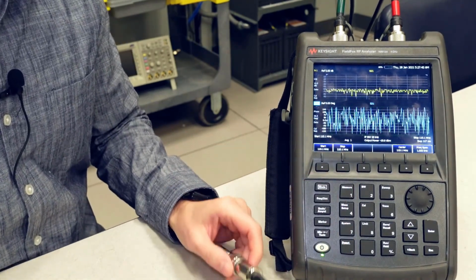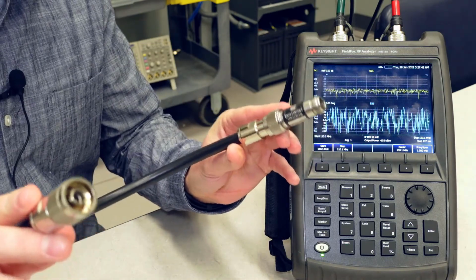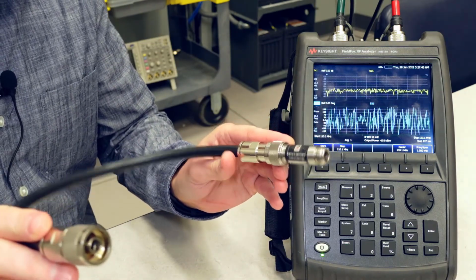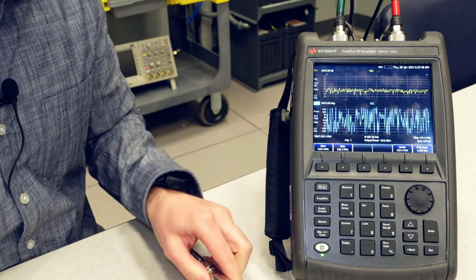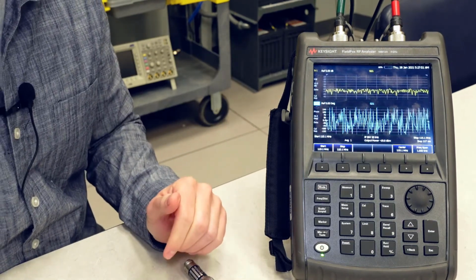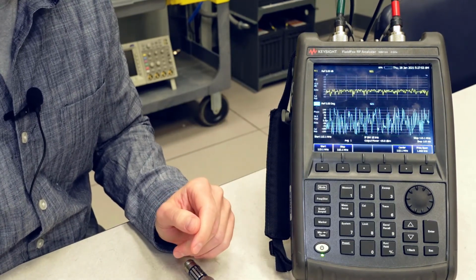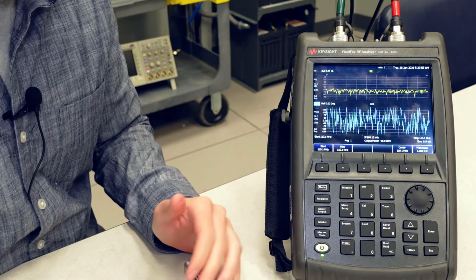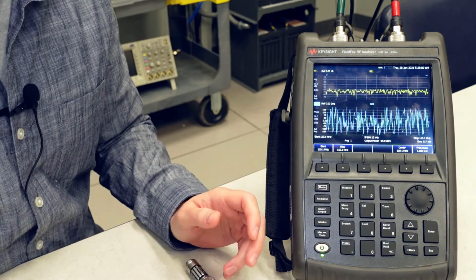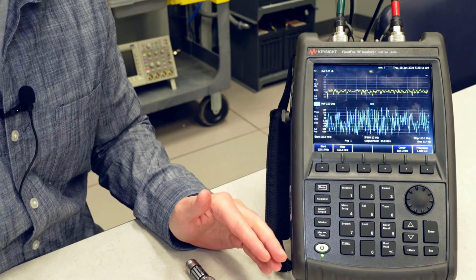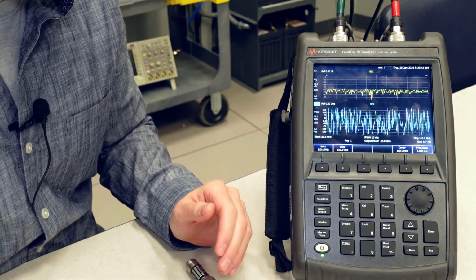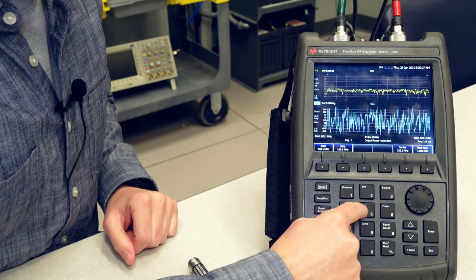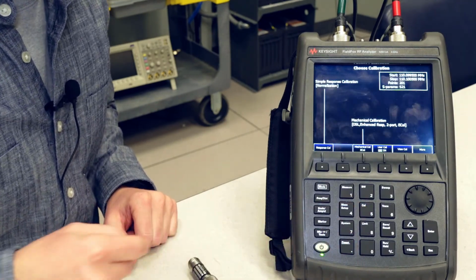which I'm not concerned with. I'm just looking at this cable and attenuator at one particular frequency, which is known as usually the station assigned frequency. When a frequency span becomes important on the network analyzer is when I'm tuning a filter that has to be a certain bandwidth, or I'm trying to tune an antenna using some impedance matchers like in the VOR. Okay, now it's time to perform calibration by hitting the number 5 calibration key.